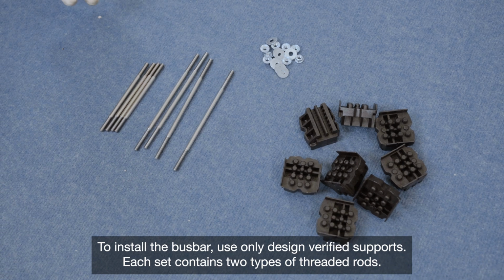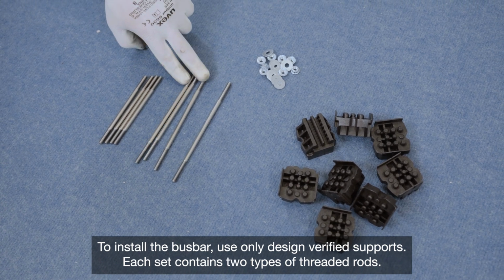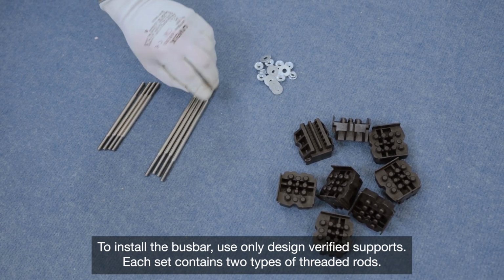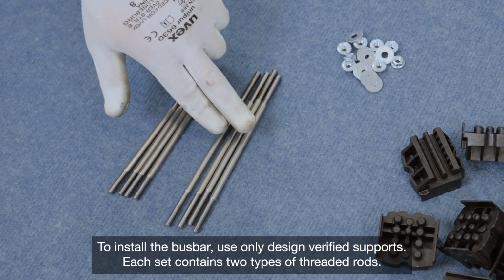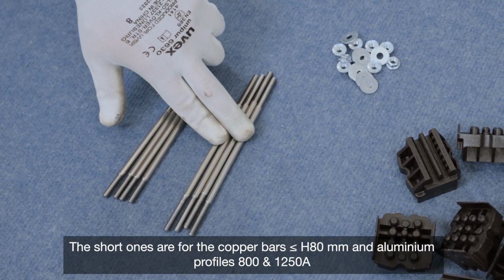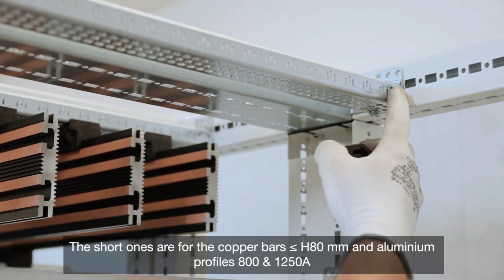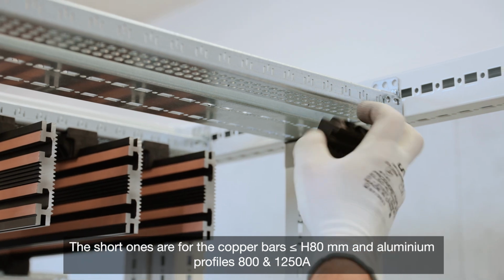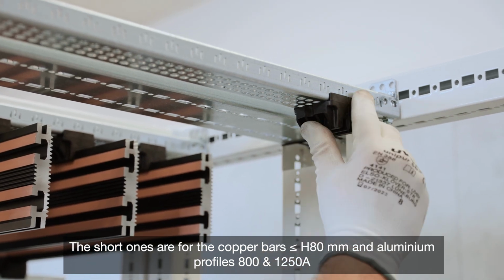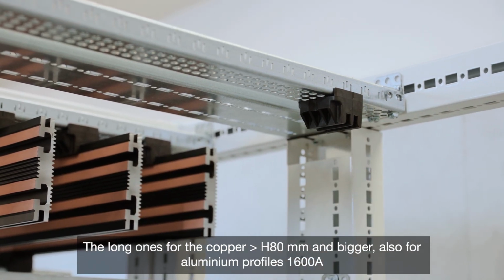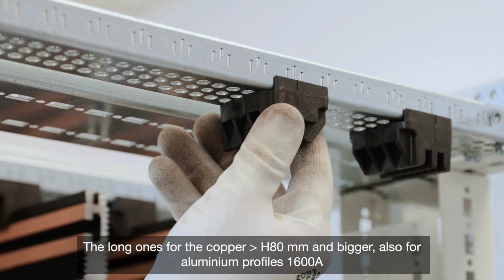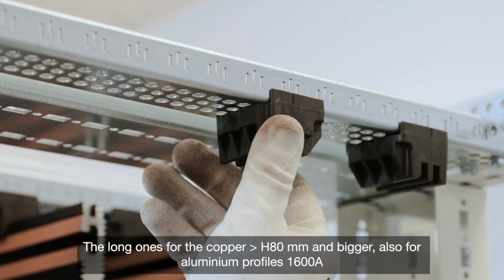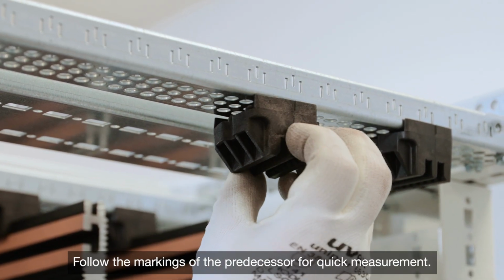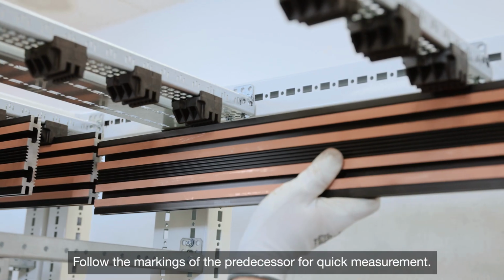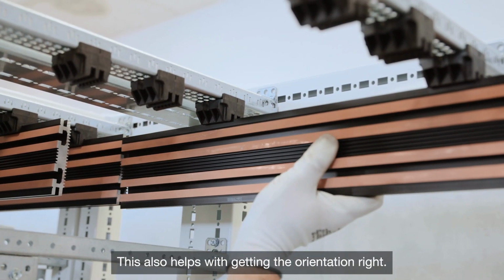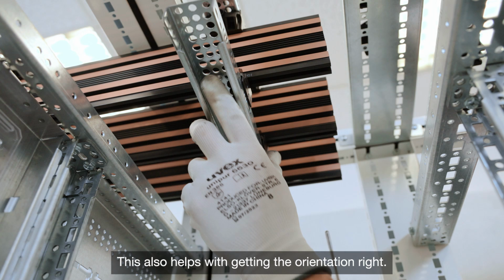be used. To install the busbar, use only design-verified supports. Each set contains 2 types of threaded rods. The short ones are for the copper bars less than or equal to H80 mm and aluminium profiles 800 and 1250A. The long ones for the copper H80 mm and bigger, also for aluminium profiles 1600A. Follow the markings of the predecessor for quick measurement. This also helps with getting the orientation right.